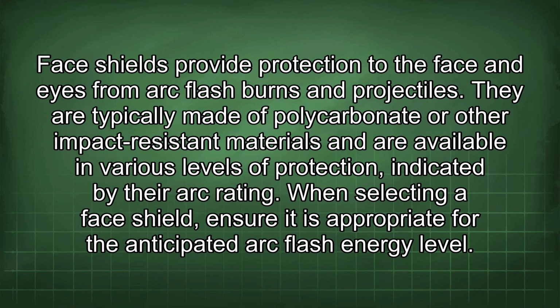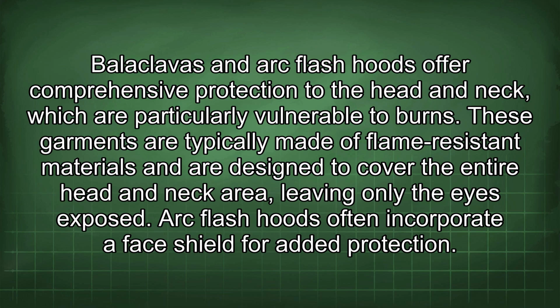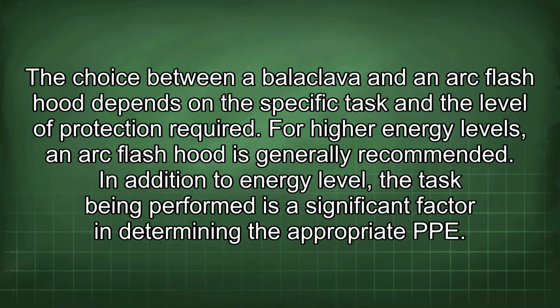Face shields provide protection to the face and eyes from arc flash burns and projectiles. They are typically made of polycarbonate or other impact-resistant materials and are available in various levels of protection, indicated by their arc rating. When selecting a face shield, ensure it is appropriate for the anticipated arc flash energy level. Balaclavas and arc flash hoods offer comprehensive protection to the head and neck, which are particularly vulnerable to burns. These garments are typically made of flame-resistant materials and are designed to cover the entire head and neck area, leaving only the eyes exposed. Arc flash hoods often incorporate a face shield for added protection. The choice between a balaclava and an arc flash hood depends on the specific task and the level of protection required. For higher energy levels, an arc flash hood is generally recommended.